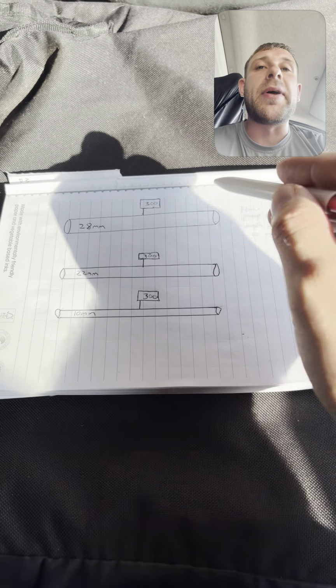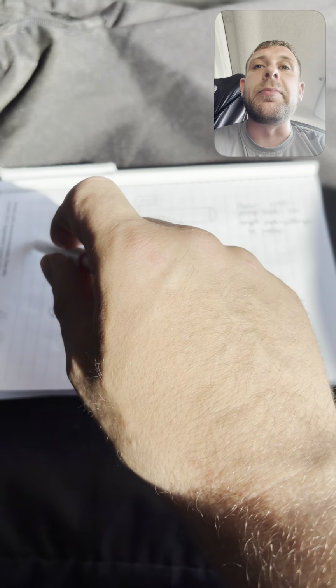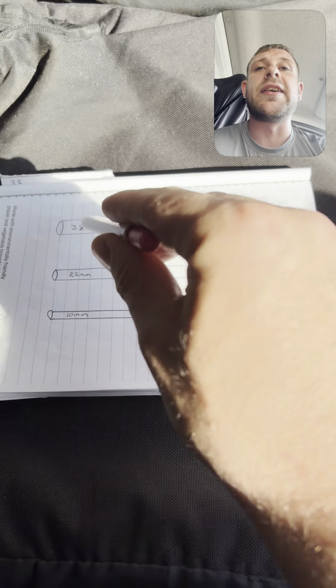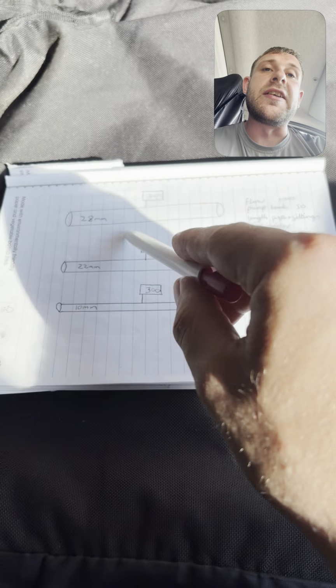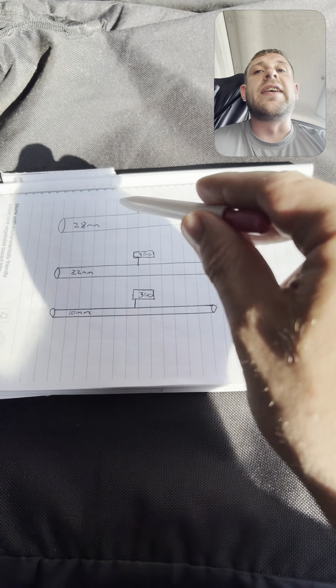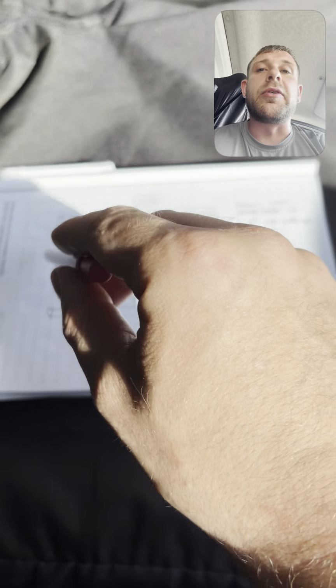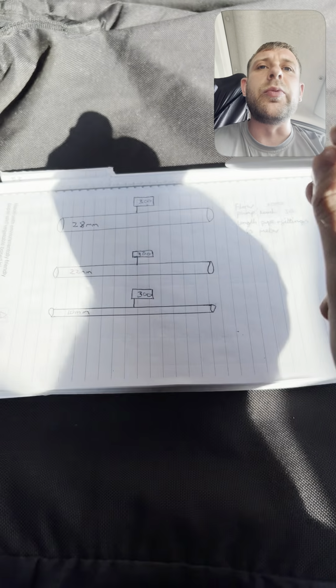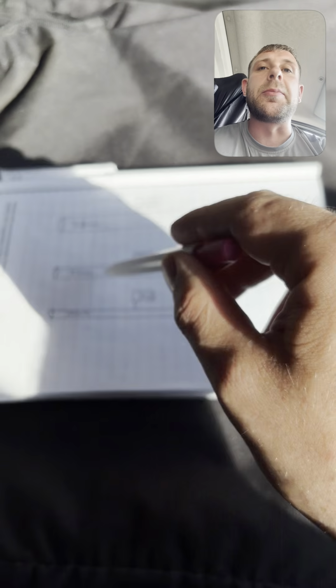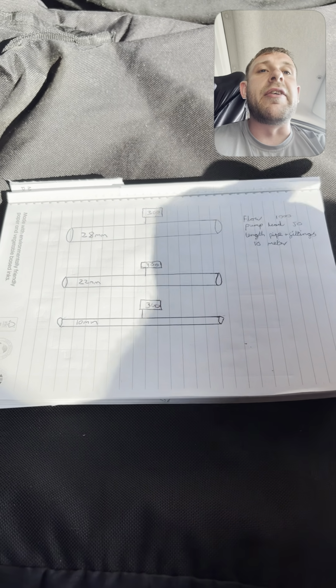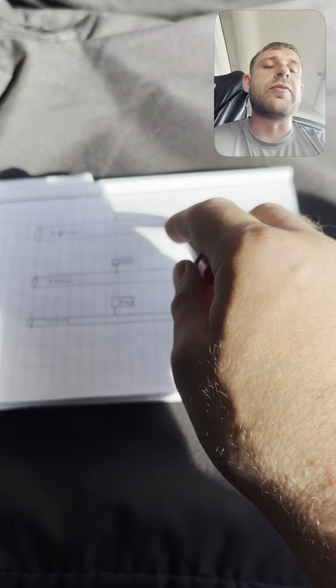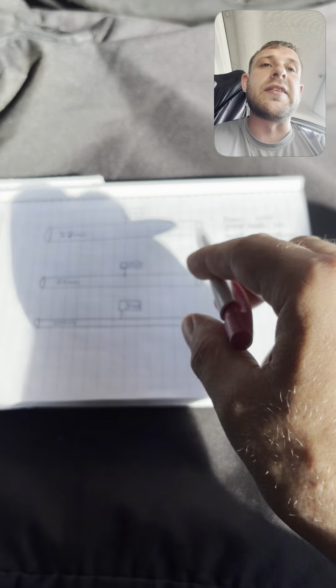Then we'll have pump head available. The heat pump will have a pump inside of it, and it'll have so much pump head available depending on what flow rate is running through that system. So let's say at 1000 litres per hour there's 50 kilopascals of pump head available. So we'll use 1000 litres per hour and 50 kilopascals. Another variable is the length of the pipe that flow rate is running through, and how many fittings are on it.